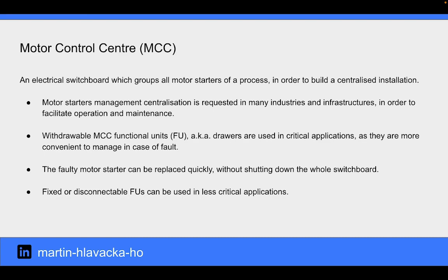Motor Control Center is an electrical switchboard that groups all motor starters of a process to build a centralized installation. Motor starter management centralization is requested in many industries and infrastructures to facilitate operation and maintenance. Withdrawable MCC functional units, aka drawers, are used in critical applications as they are more convenient to manage in case of fault. The faulty motor starter can be replaced quickly without shutting down the whole switchboard. Fixed or disconnectable drawers can be used in less critical applications.